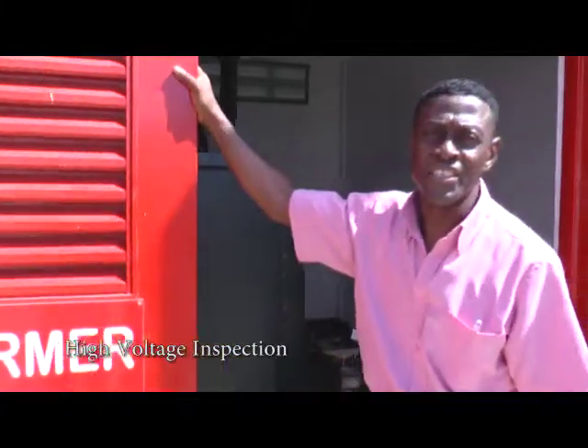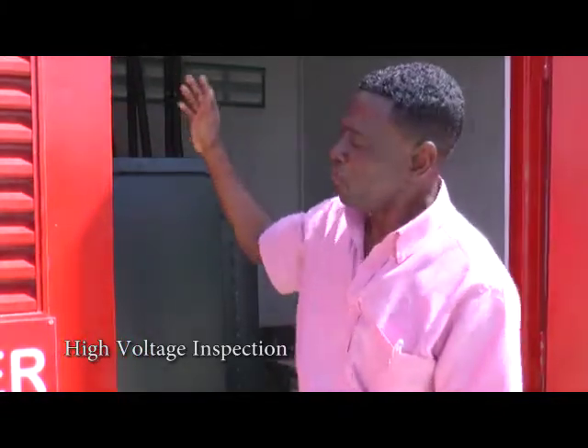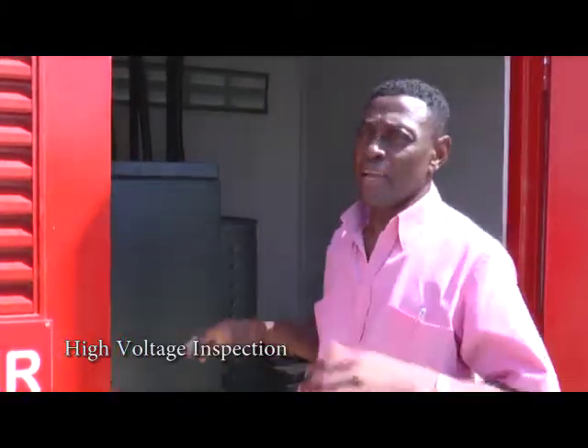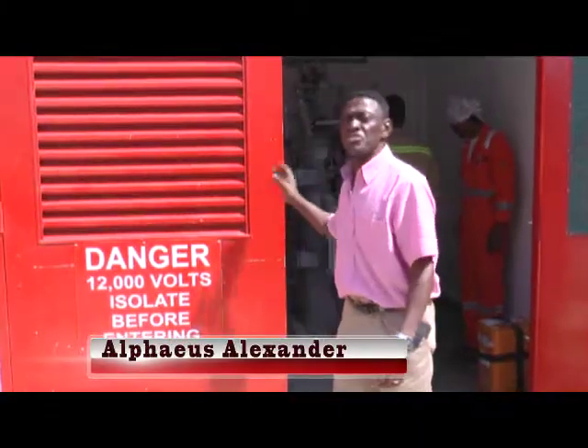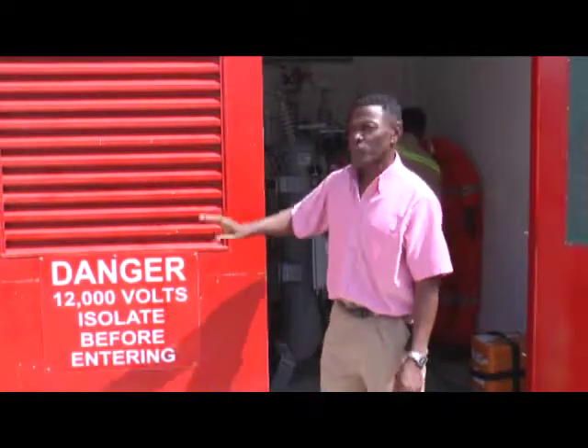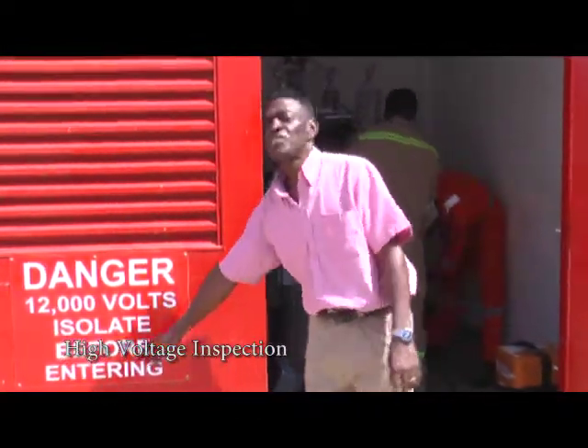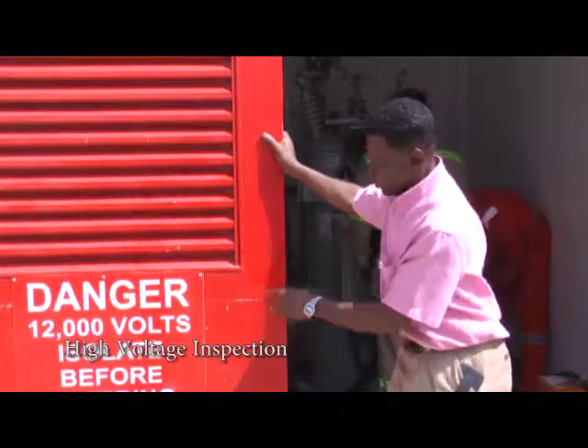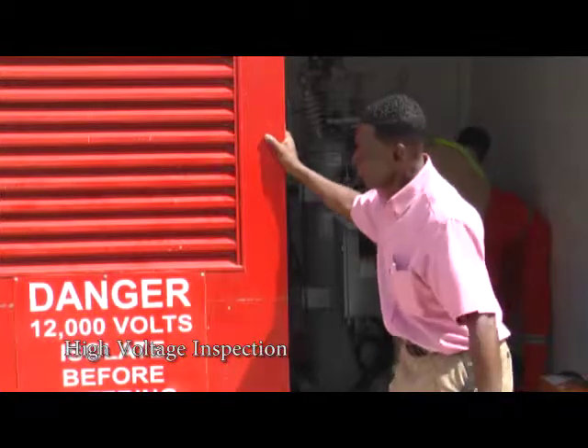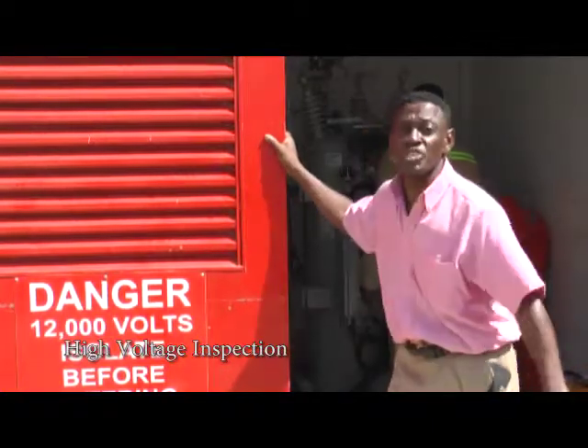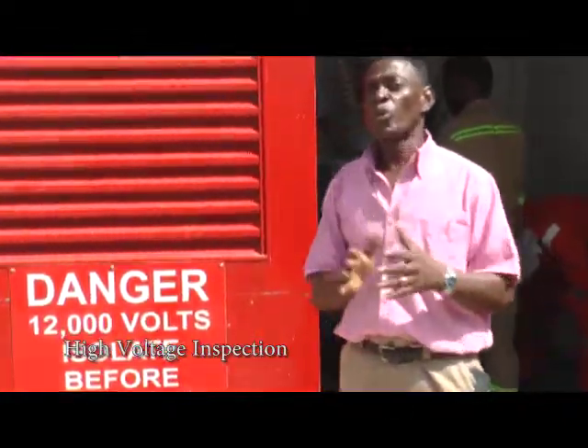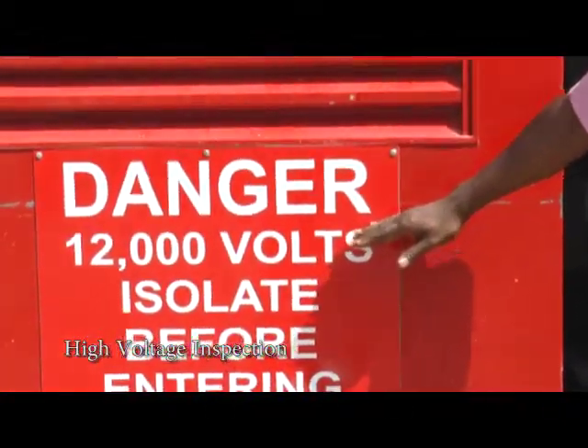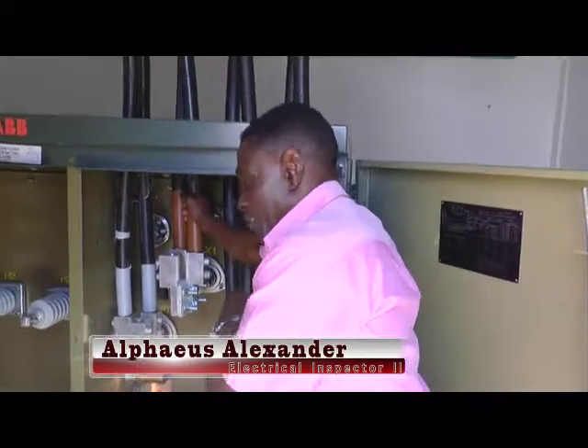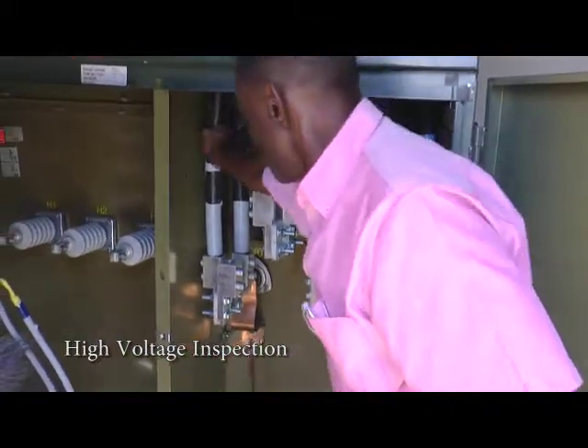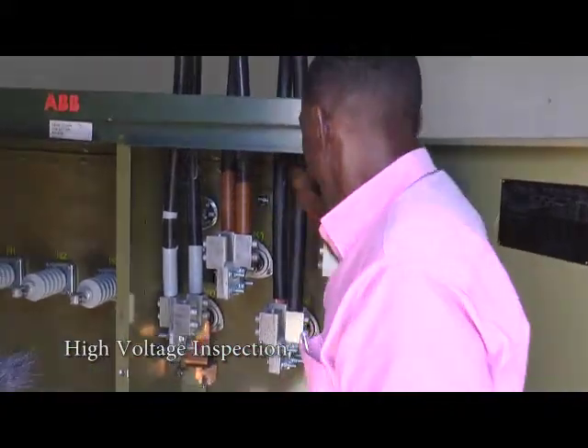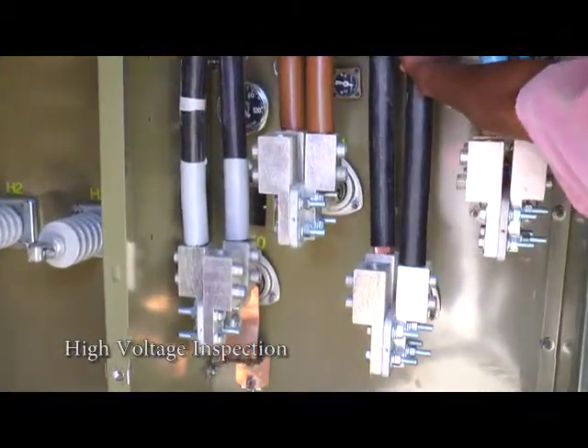Transformer area must be isolated at all times. It is only opened when the supply is disconnected to the transformer room. Because of the seriousness of this installation, all signs, danger 12,000 volts, isolate before entering, must be placed on all transformer rooms, regulator rooms, high voltage regulator rooms, and switchgear. This is to indicate that no one should enter because of the seriousness of this installation. Termination, the lugs must be securely anchored, ensuring that there are no slack connections, as this could result in dangerous arcing.